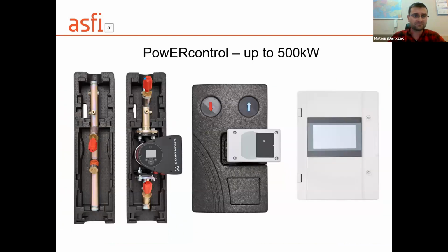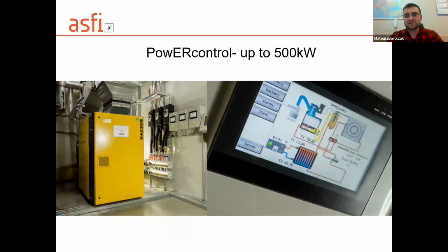Power Control, as I said, is a pump group and controller with a power control algorithm. Of course, the pump group is matched to the compressor power. And here is an example of implementation from a glass manufacturer. The client's compressor had heat exchangers, and together with Power Control they create a recovery system.